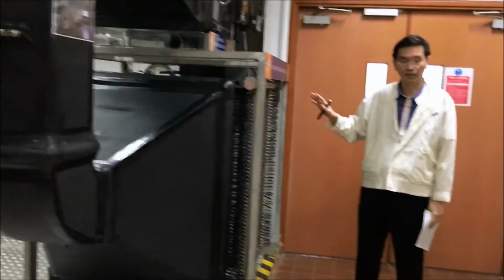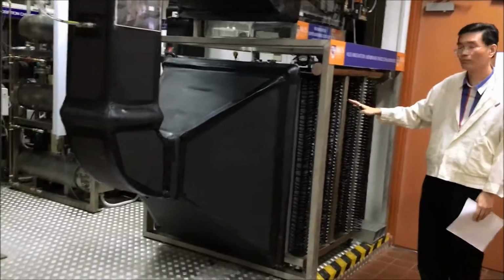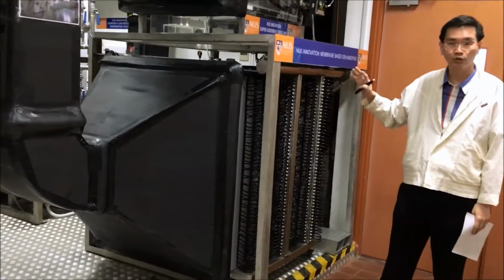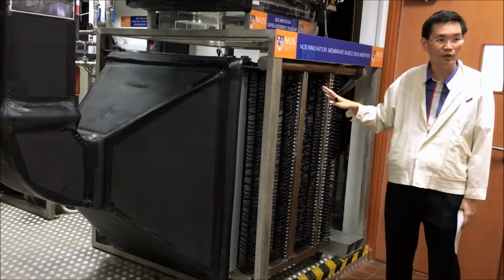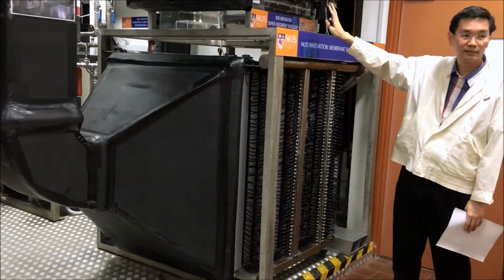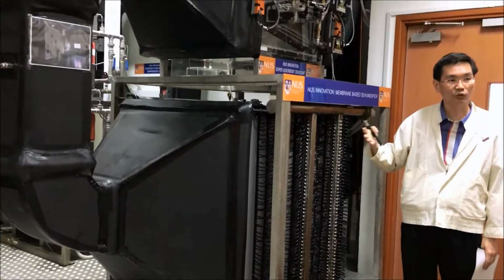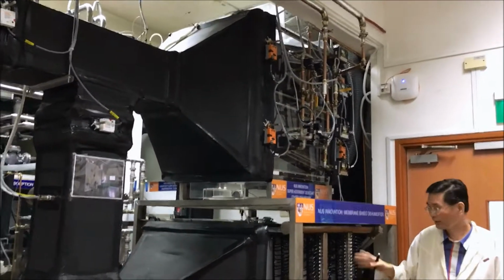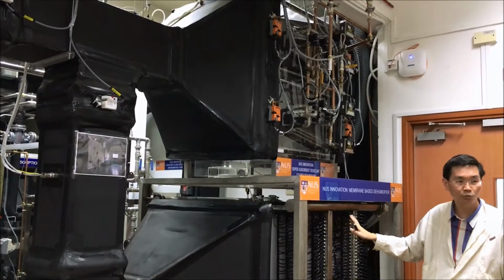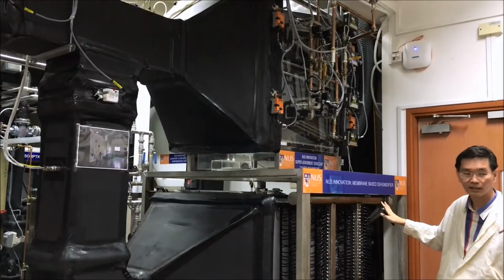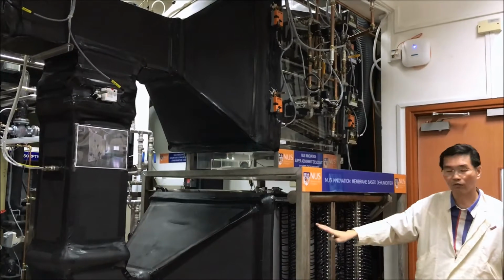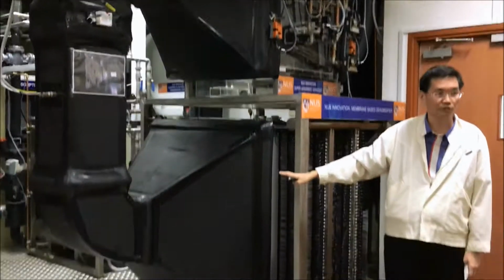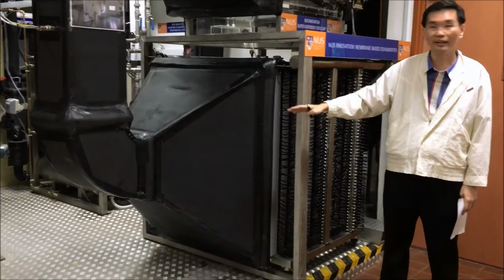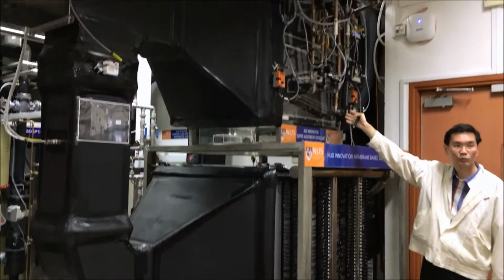And over here, we can see another two key innovation technologies that have been developed for this project, which is the membrane dehumidifier. Right? So for systems like this, if the air is really dehumidified using membrane and super absorbent, then the chilled water temperature only needs to take care of the sensible cooling. So here the membrane can cool the air from outdoor humidity of about 22 to about 10 grams per kg of dry air.